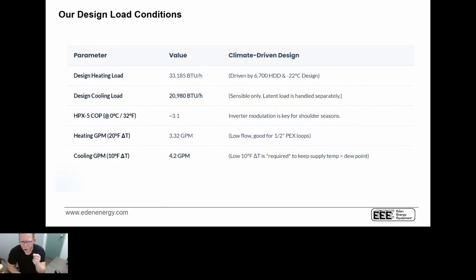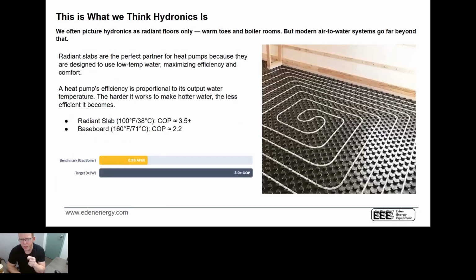So we're going to dig into what this means and how we can achieve this. We're going to start with a very basic heating system. This is a heating system we would all be familiar with, right? This is a photo that was supplied to me by a customer. And this is just your classic radiant floor heating system. So the reality is, if you were to look at the COP of an air to water heat pump, regardless of who makes the unit, and if you were to assume about 100 degrees throughout the wintertime, 90% of the time, you can probably achieve a COP of 3.5, which means the unit is 350% efficient.